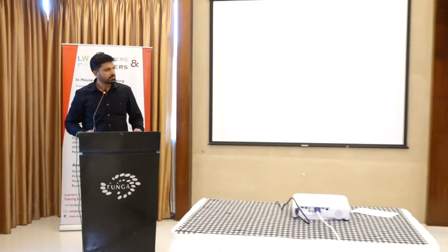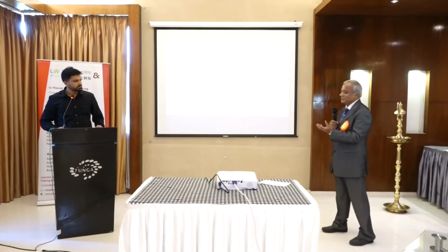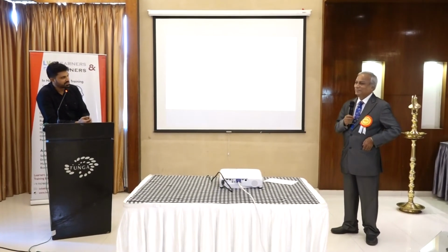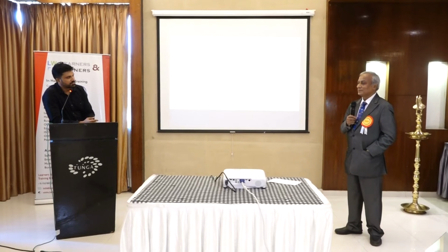Sir, I will just support his question. In a marshalling box, in a transformer cable terminal box, why don't you put silica gel, a simple solution? Transformers come with silica gel. Then what is the issue? Why are you still getting moisture?